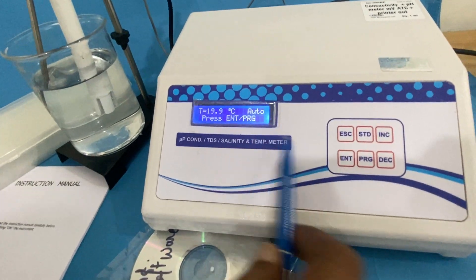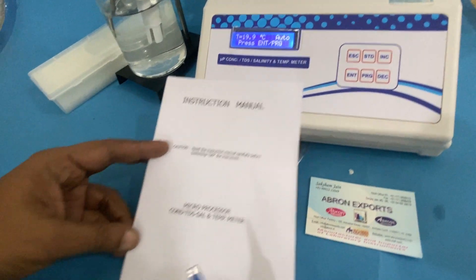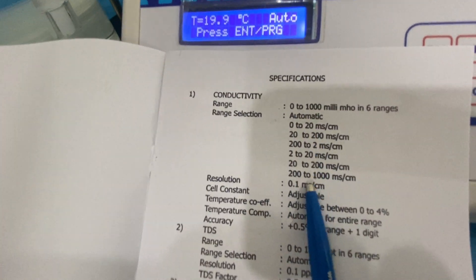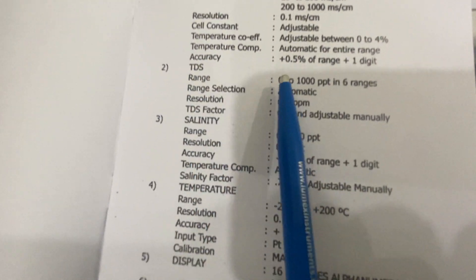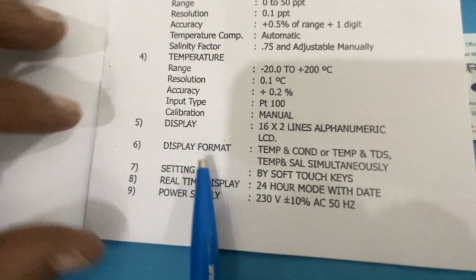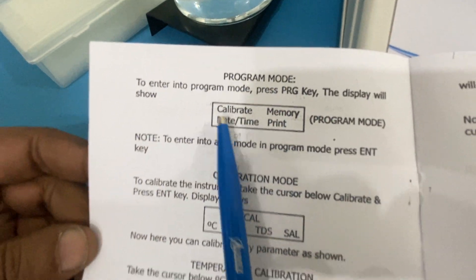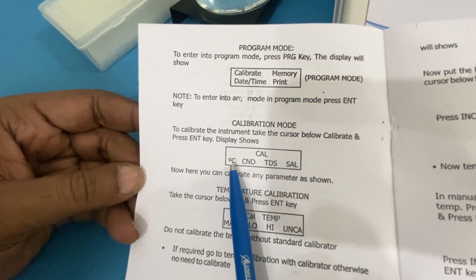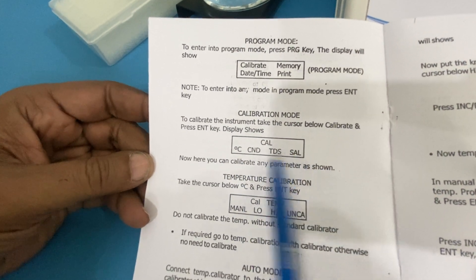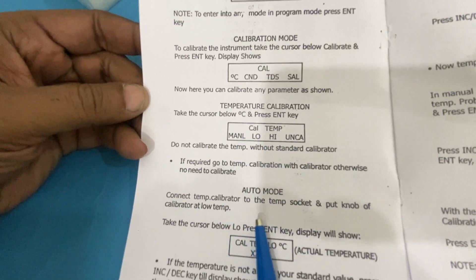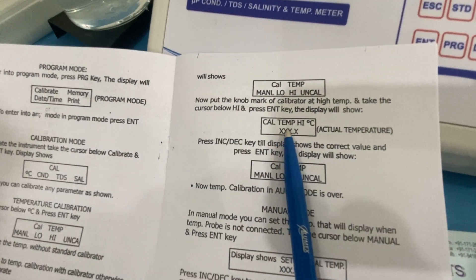Similarly, you can check all other parameters. The manual is very easy to follow — it tells you conductivity, all ranges, cell constant, TDS, salinity, temperature display, and similar items. It also tells you the program mode, how to enter it, the calibration mode, temperature and salinity calibration, automatic mode, and manual mode.